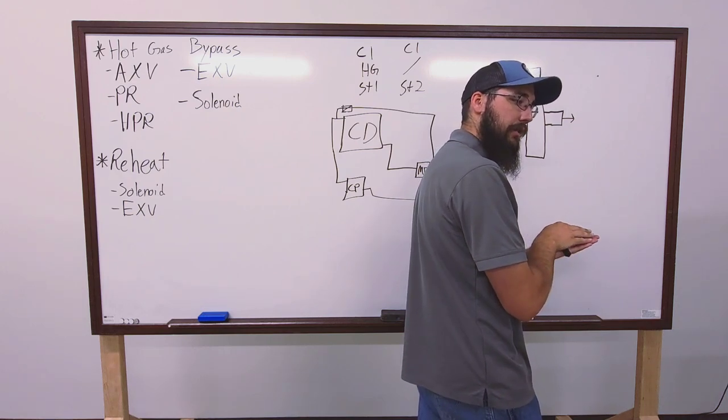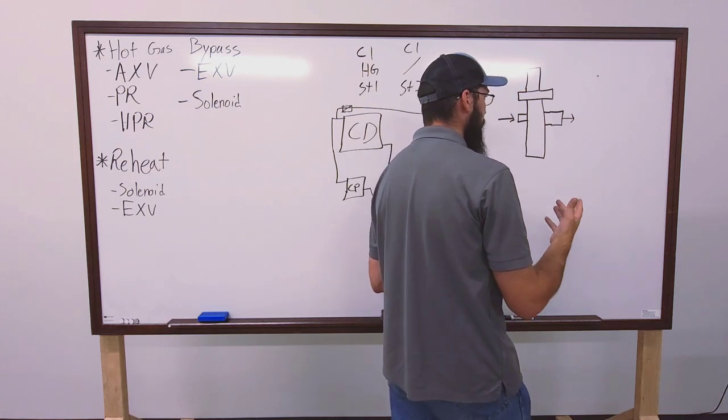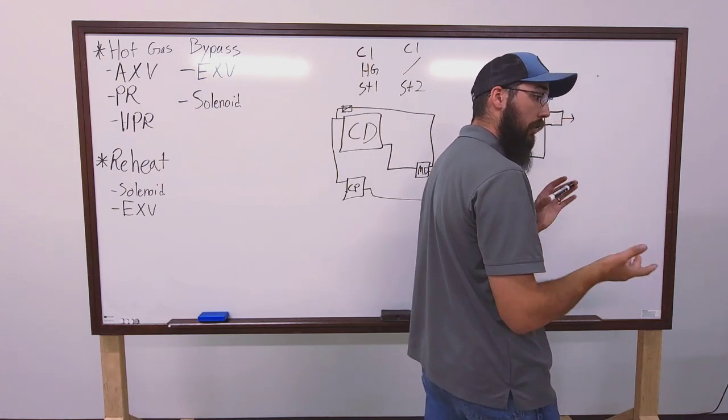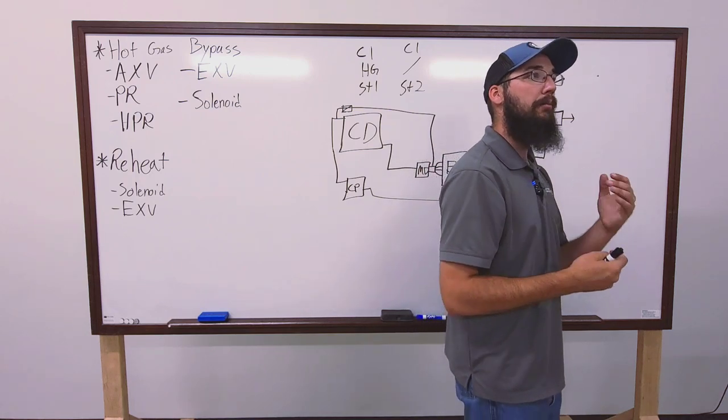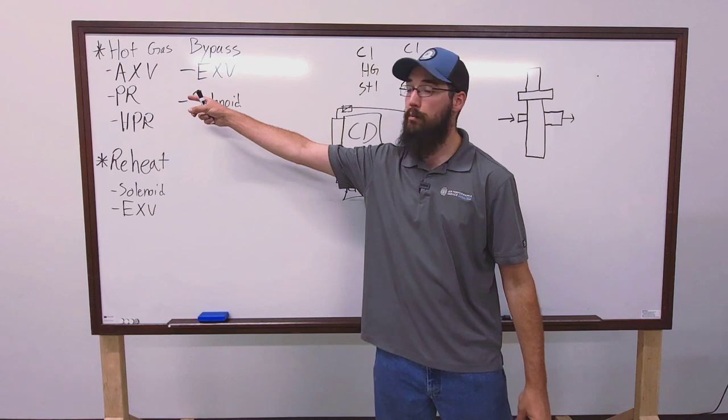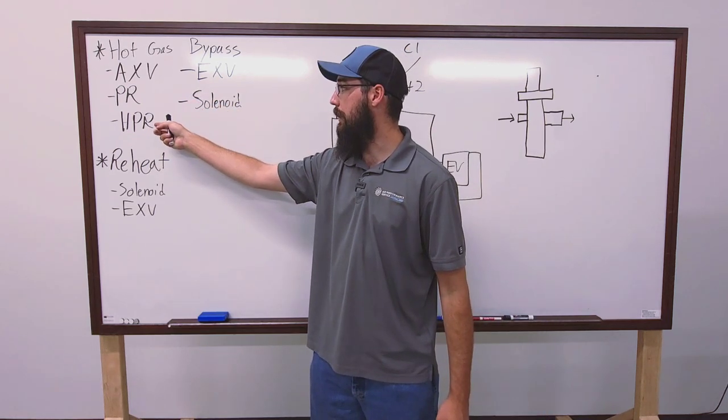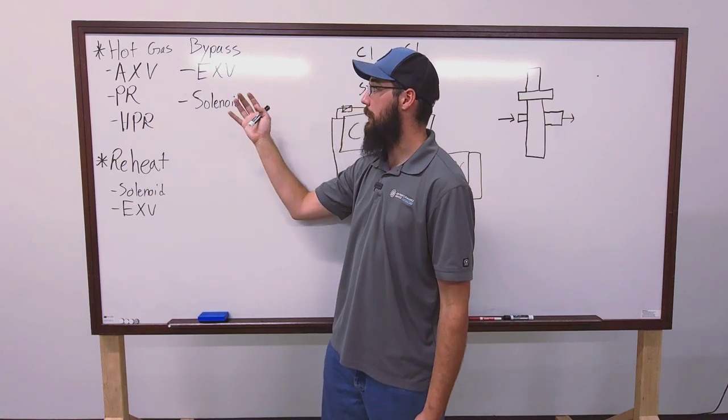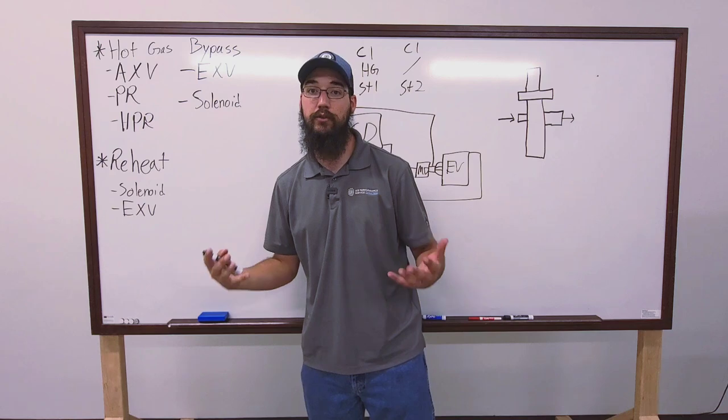To allow pressure to flow. Right, it's controlling a differential. Ultimately, that's what AXVs do. They are a pressure differential control device. Which, so is a pressure regulator. And, technically, so is a... Honestly, if we really got down to it, short of a solenoid, it's what all these do. They control pressure differential across them. Now, in reality, these three are specifically designed to operate off of pressure differential.